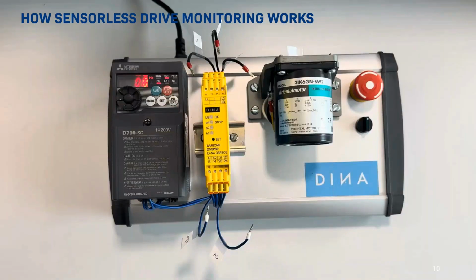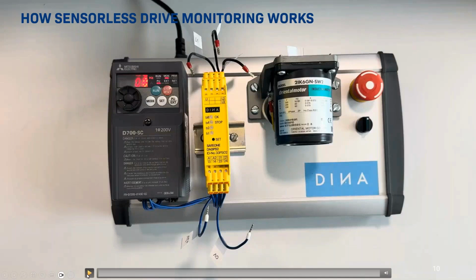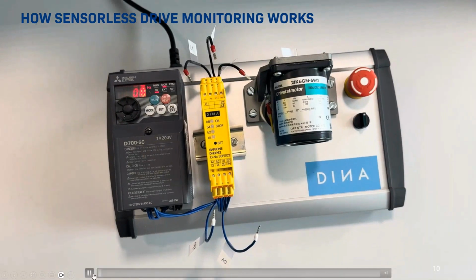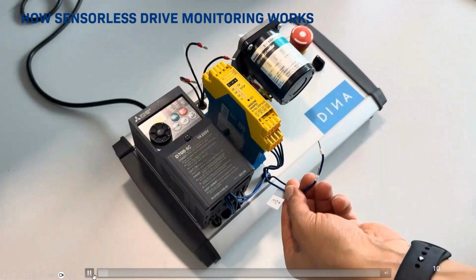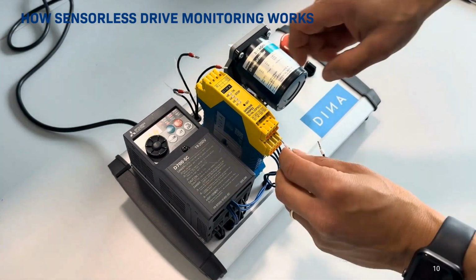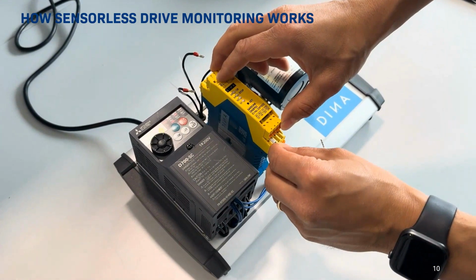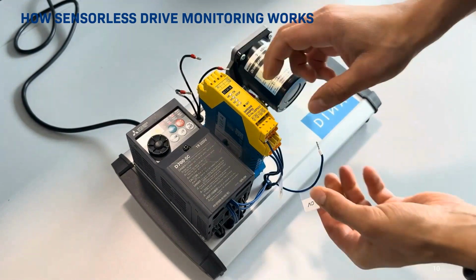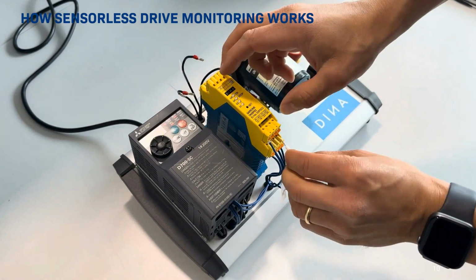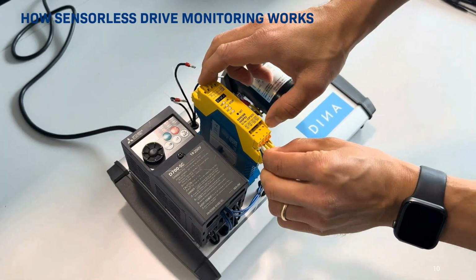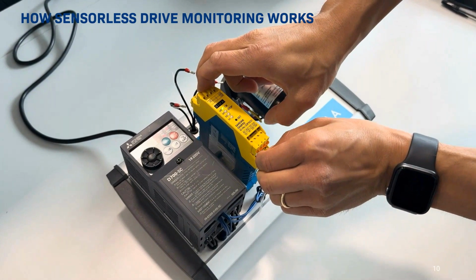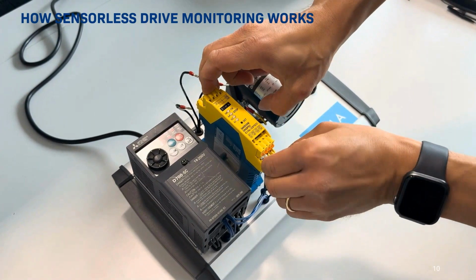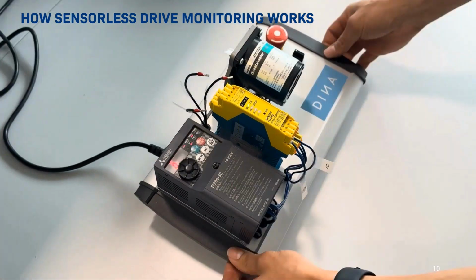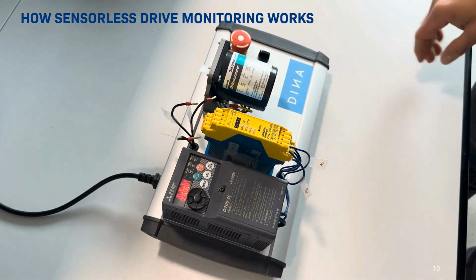Now we see a short video with a demonstration. Here we see a SafeOne sensorless module. All of our sensorless module variants will be installed in a similar way, independently of whether it's a speed monitor or standstill monitor. The first thing you need to do is connect the 24-volt power supply and the safety input or output signals for start signals or acknowledge commands.